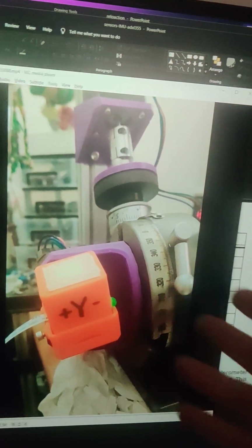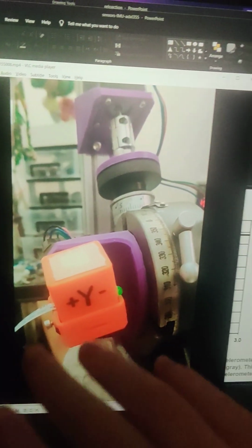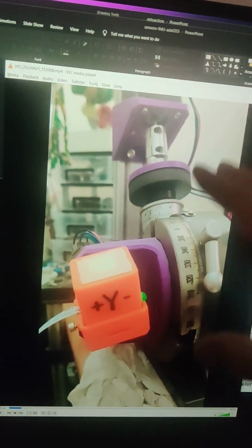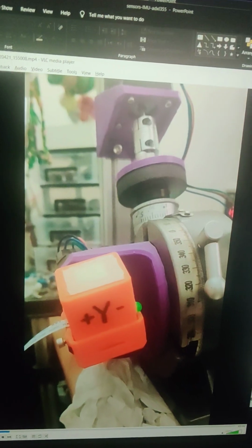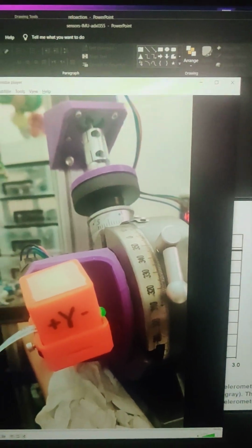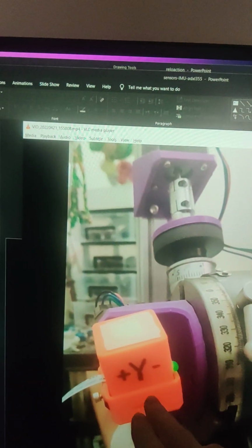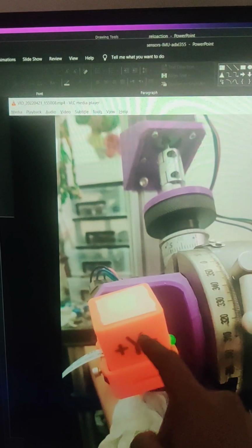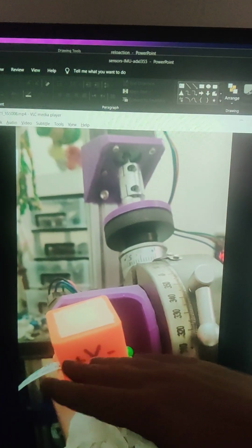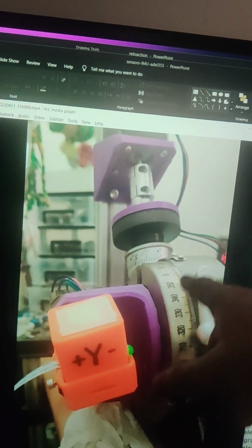So what I'm doing here is trying to gain more precision along the whole range of the sensor. Usually you get a very good result close to 0, but as you proceed you start to lose it. So this is what I'm doing in the device. First of all, I'm balancing. There's a stepper motor on the other side of this box right here. We see the cable. It will balance just the Y, because I want the Y to be at 0. And then I will balance the X-axis with this. I will explain in a second.